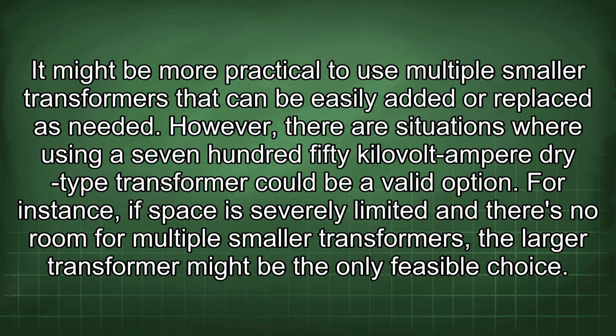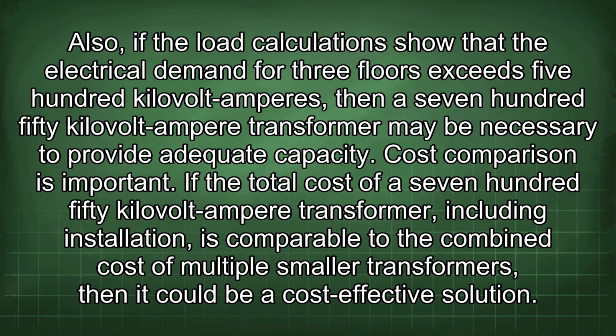For instance, if space is severely limited and there's no room for multiple smaller transformers, the larger transformer might be the only feasible choice. Also, if the load calculations show that the electrical demand for 3 floors exceeds 500 kVA, then a 750 kVA transformer may be necessary to provide adequate capacity. Cost comparison is important. If the total cost of a 750 kVA transformer, including installation, is comparable to the combined cost of multiple smaller transformers, then it could be a cost-effective solution.